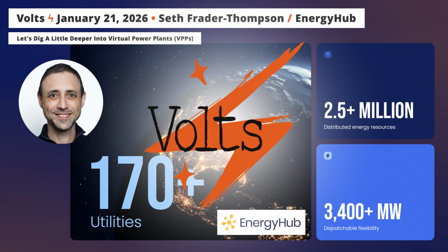The one other thing that people don't talk about a lot here, but is becoming more and more important as a result of climate change, is that most of the limits we talk about in the physical grid are thermal limits. There's some piece of equipment that you put enough power through, it gets too hot, and some component in that is going to wear out. A lot of the time you have a decent amount of cushion, that thing can get pretty hot for a few hours so long as it has a chance to cool down overnight. Well, what if it doesn't cool down overnight?